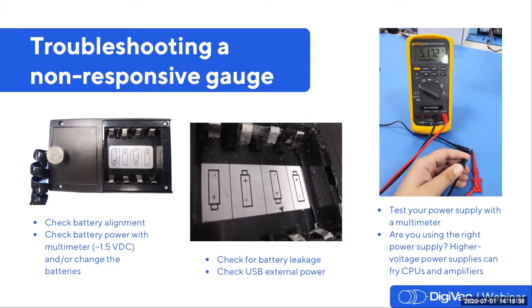If your power supply tests okay and the gauge still will not turn on, consider if you or someone in your facility has attempted to power the gauge with an incompatible supply. We see these gauges in the repair queue quite often. A person has mistaken a 24-volt supply for the appropriate 5-volt supply, and higher voltage supplies will damage the CPU, amplifier, and possibly the integrity of the printed circuit board, meaning the gauge needs to be remitted to us for repair.